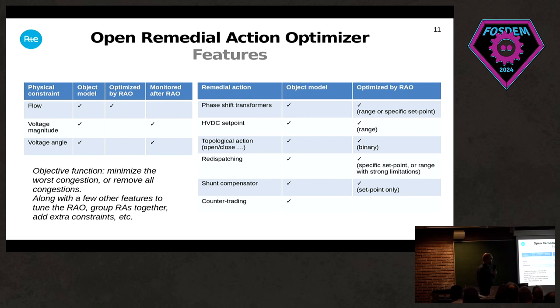For remedial actions, we can optimize phase shift transformers in a given range. So if you give the RAO a range of possible tap positions for the phase shift transformer, it will choose the most optimal one that reduces congestions over the whole network. We can also optimize an HVDC set point, so it can change the set point of the HVDC to reduce constraints.